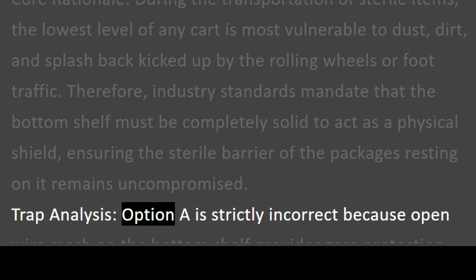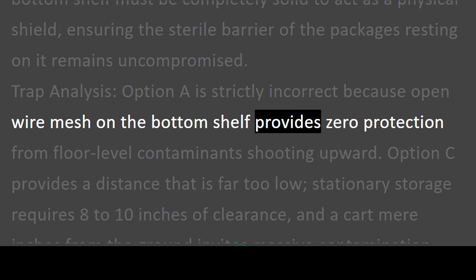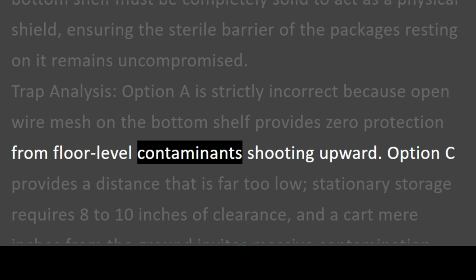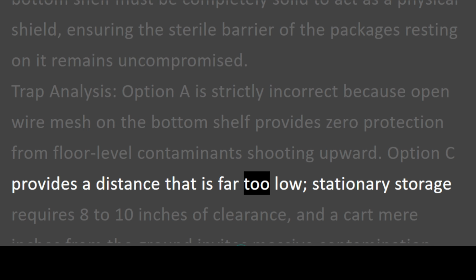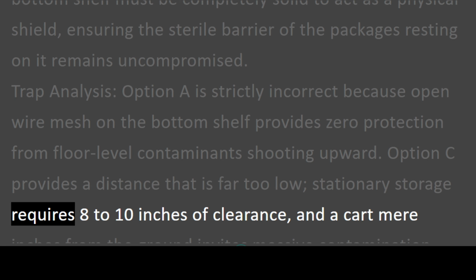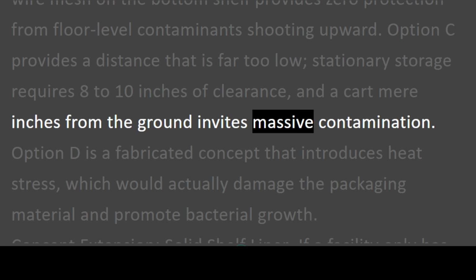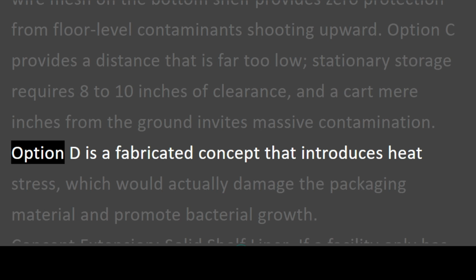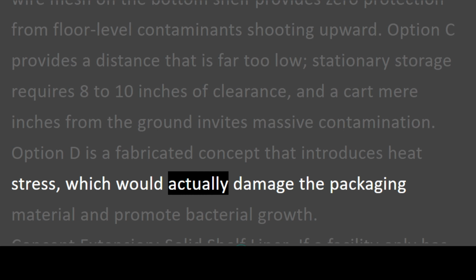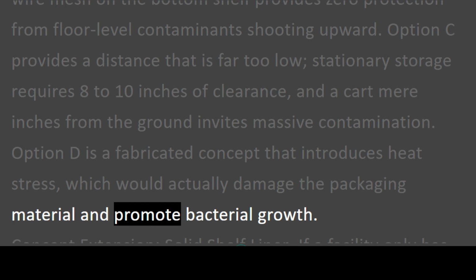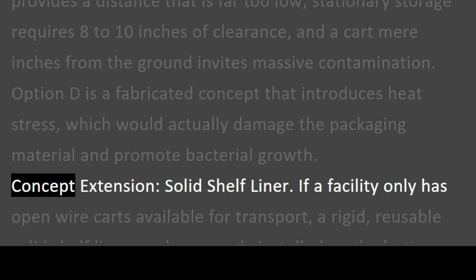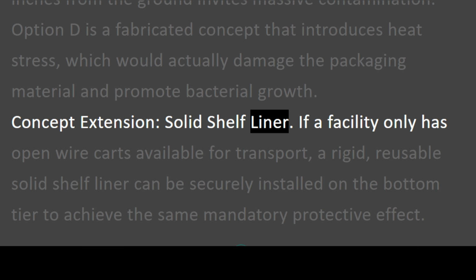Trap analysis. Option A is strictly incorrect because open wire mesh on the bottom shelf provides zero protection from floor-level contaminants shooting upward. Option C provides a distance that is far too low. Stationary storage requires 8 to 10 inches of clearance, and a cart mere inches from the ground invites massive contamination. Option D is a fabricated concept that introduces heat stress, which would actually damage the packaging material and promote bacterial growth. Concept extension, solid shelf liner.